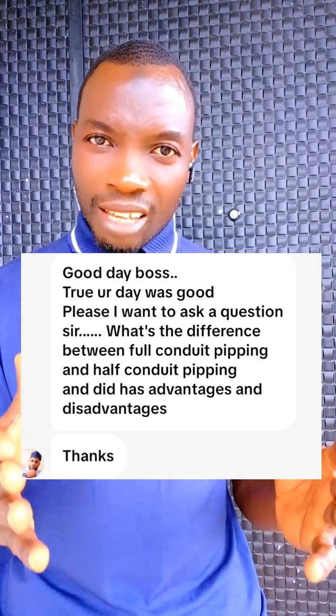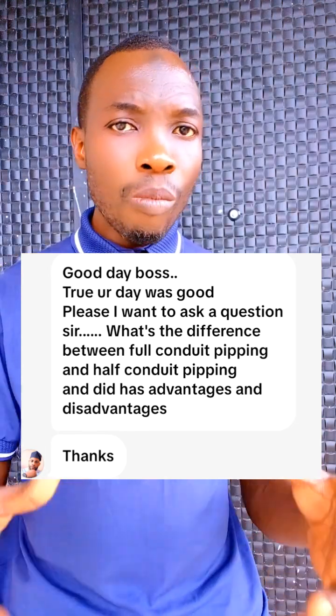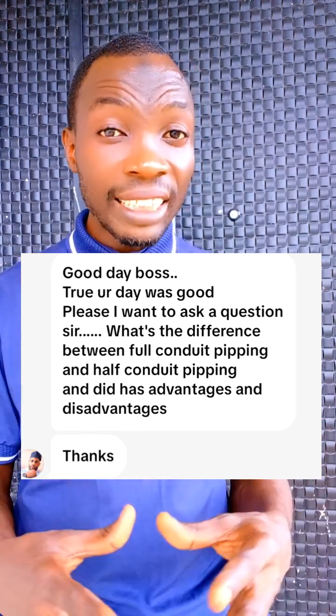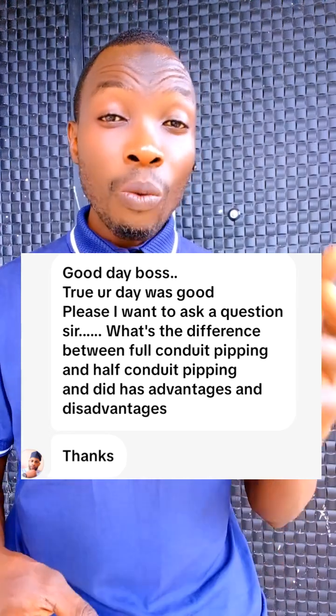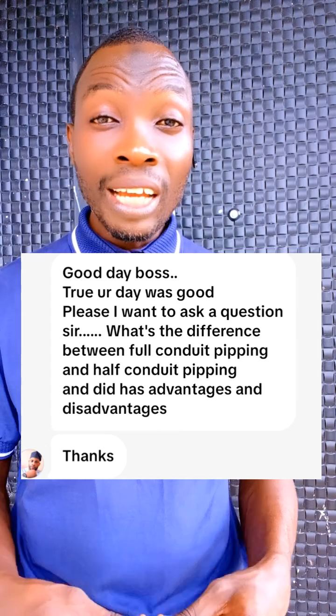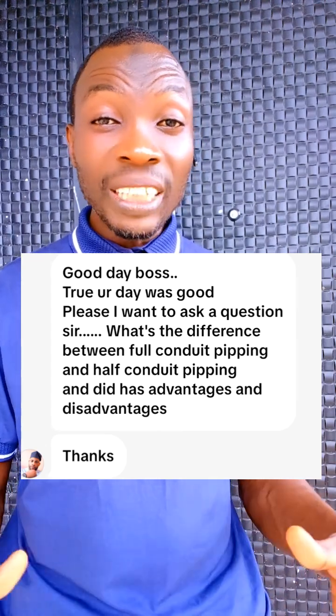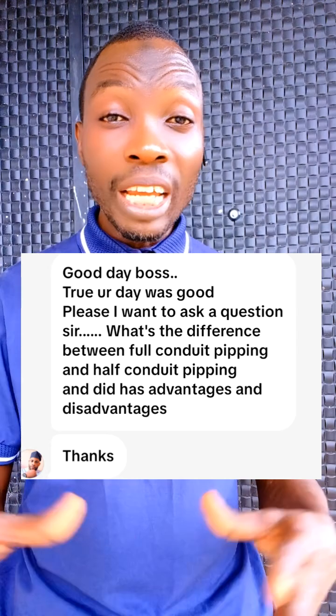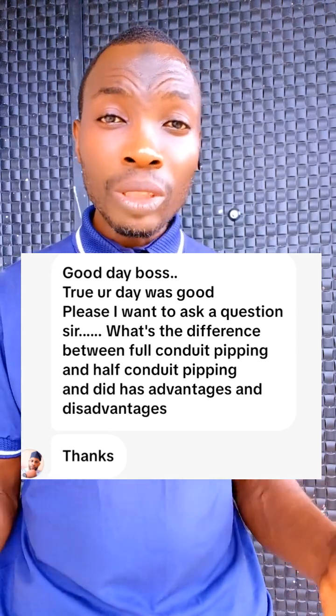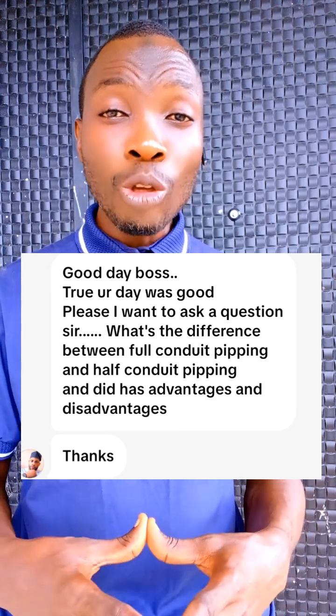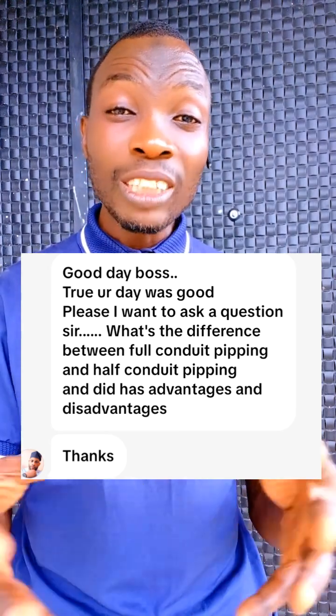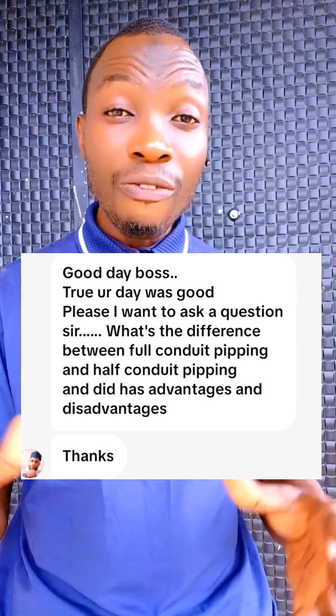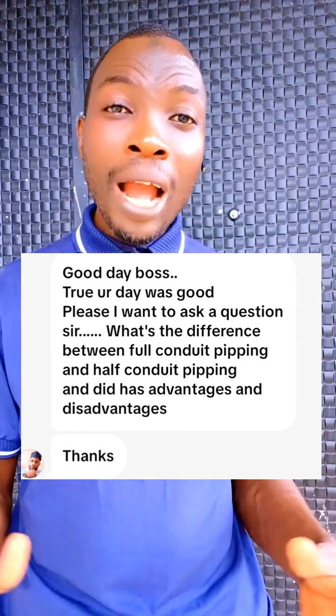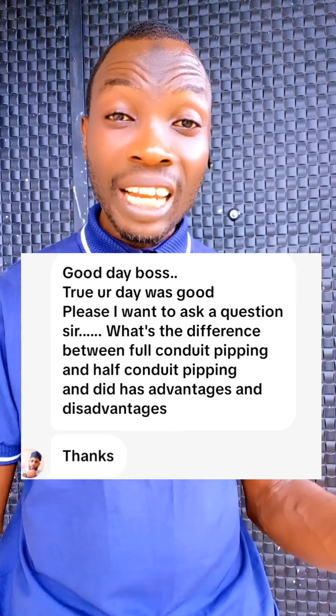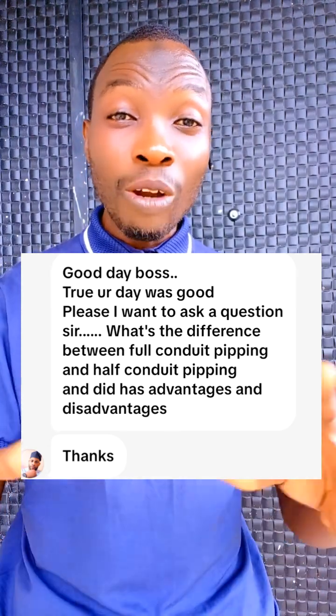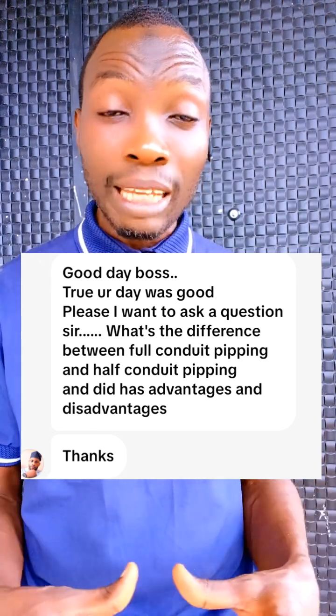But the other way around, most electricians, as I said in one of my past videos, when they want to carry out full conduit, exceed the space factor which is allowed in conduits. In conduits, you are allowed to make use of 75% of the total space available in the pipe, while the remaining 25% is left as space in order to have a reasonable ambient temperature.